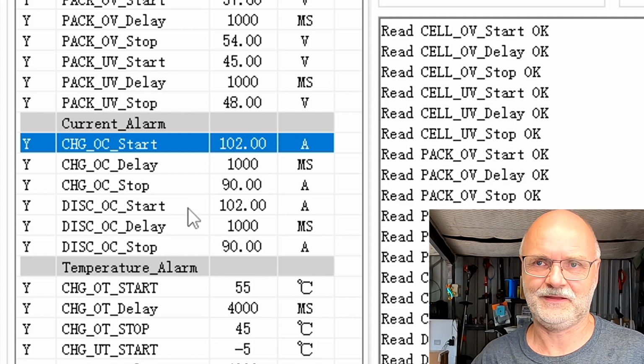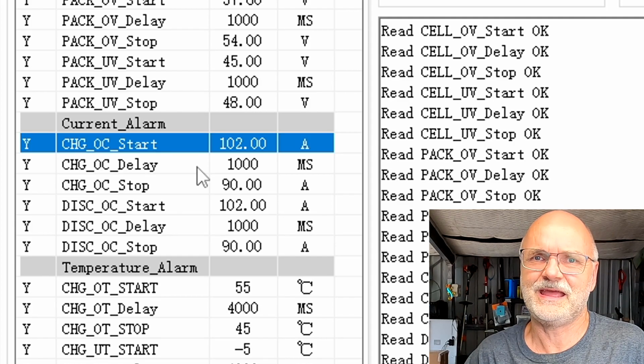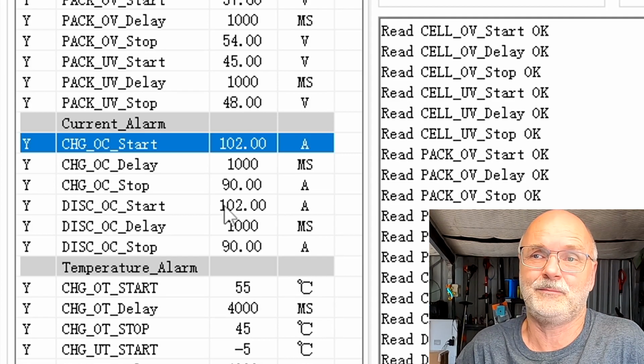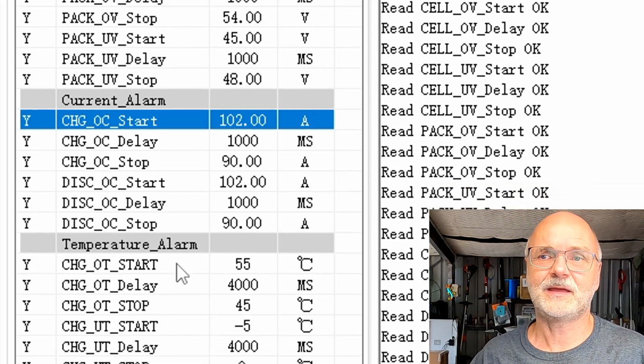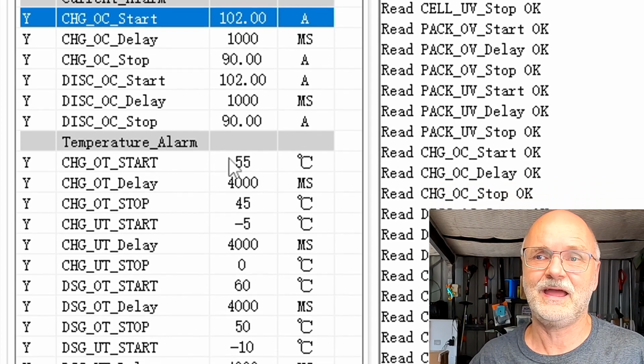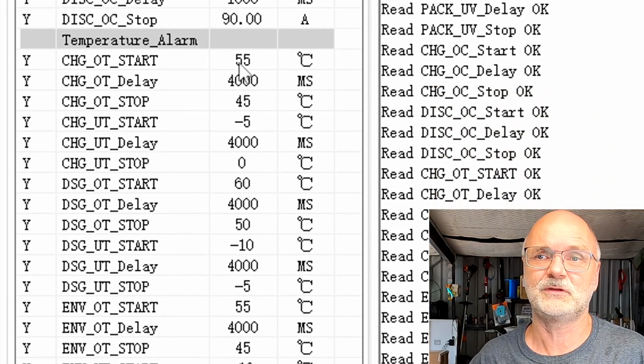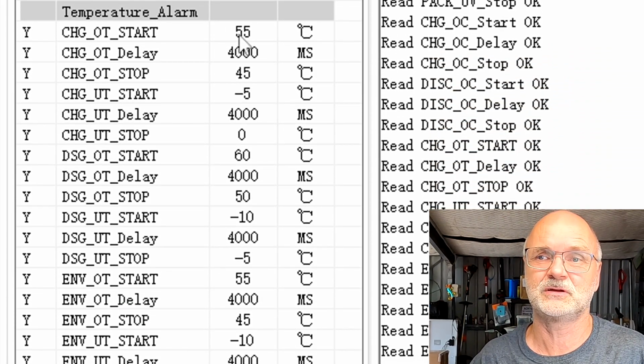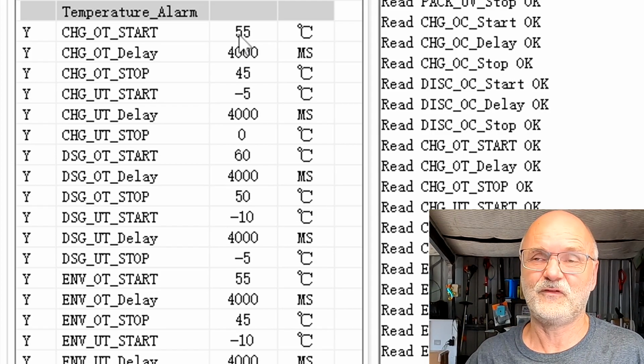Answers are outstanding. And if it is a 250 amp BMS, you don't want an alarm at 102 amps, right? You definitely not. And same for the discharge overcurrent. 102 amps is far too low. If it's even a 200 amp BMS, it's far too low. Okay, the temperatures, well, they are still very high. I would set them lower. 55 degrees is an alarm for the over temperature. This should be sitting at like 45 or something.